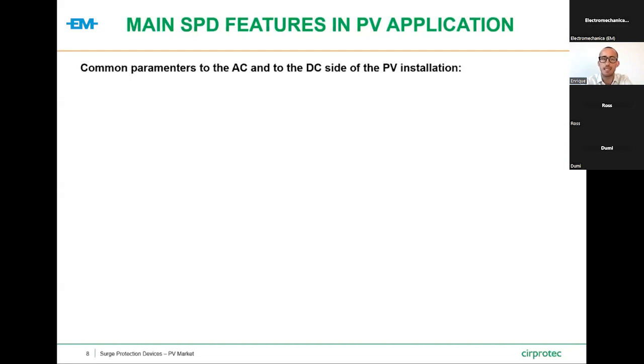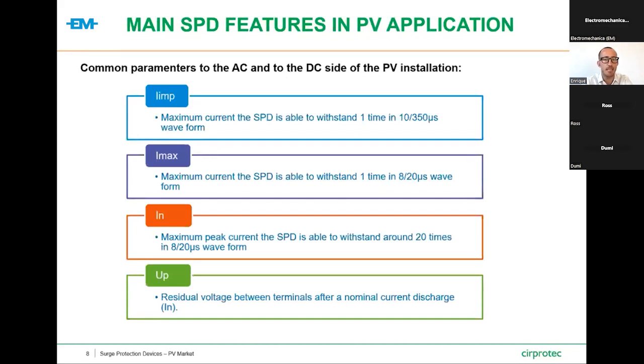Now it's time to check together the main SPD features in the PV application. Let's start with the common parameters to the AC and to the DC side of the PV installation. The first one is the Iimp, which means the maximum current the SPD is able to withstand one time in the waveform of conduction. Then we have the Imax, which means the maximum current the SPD is able to withstand one time in the waveform of induction or internal sources.